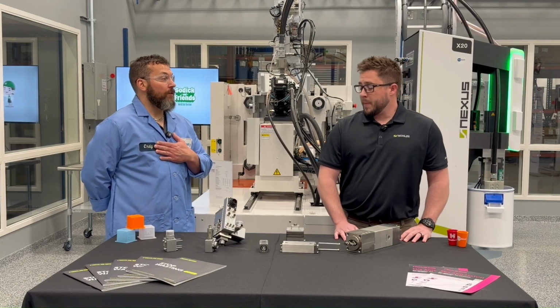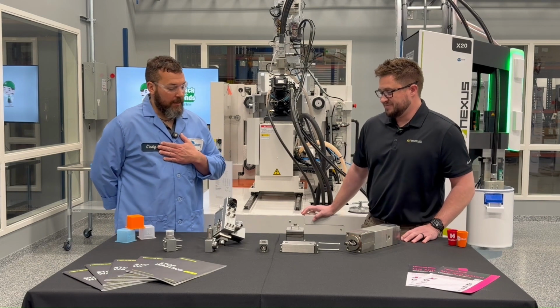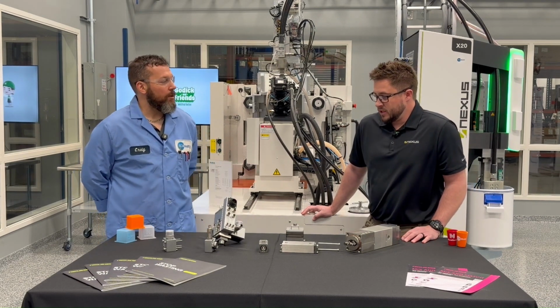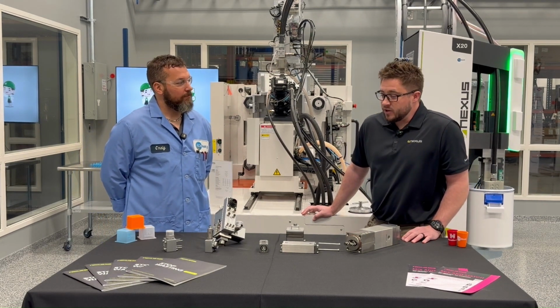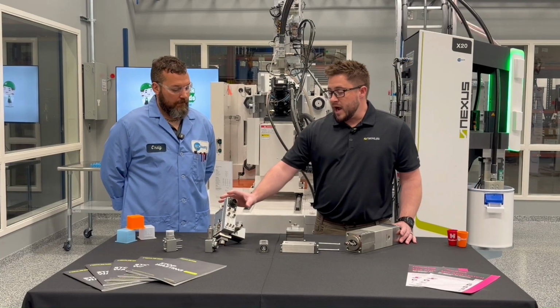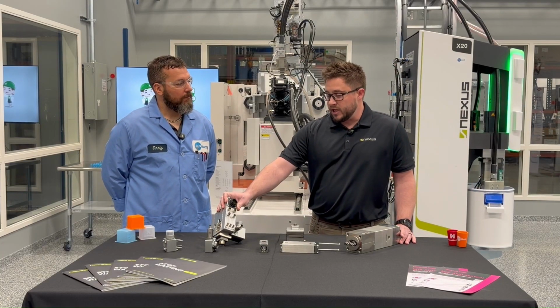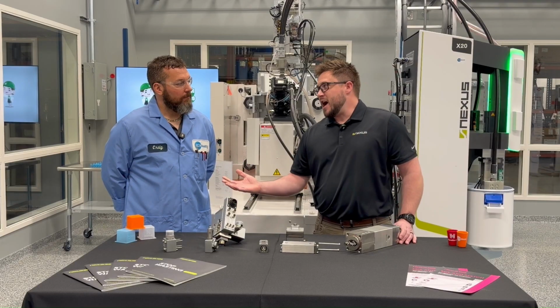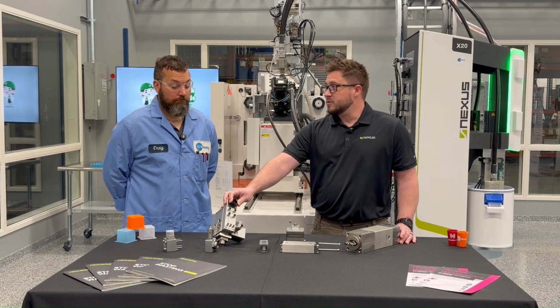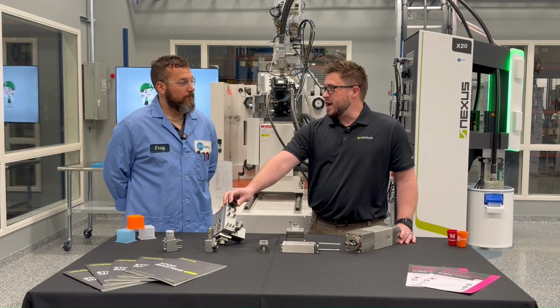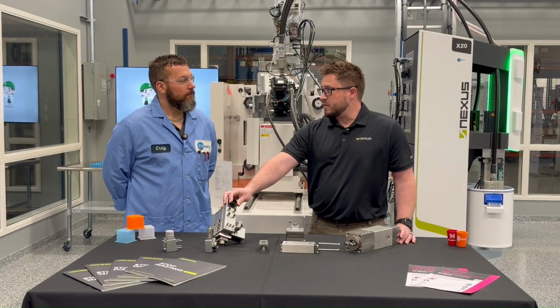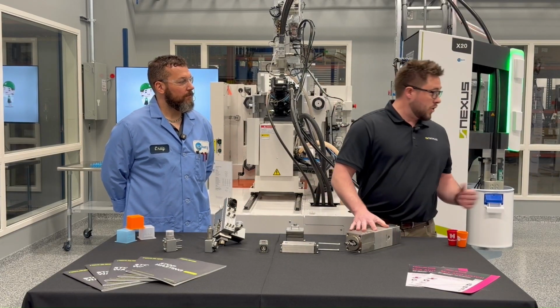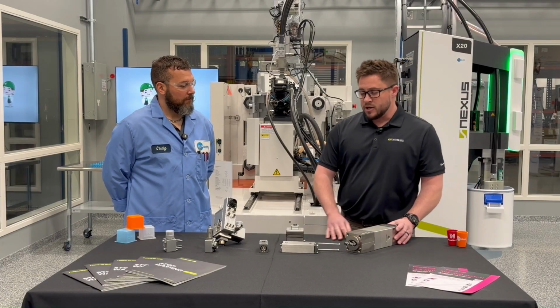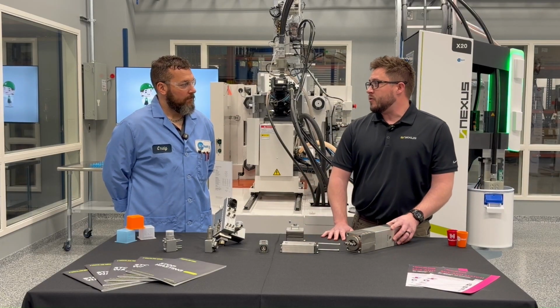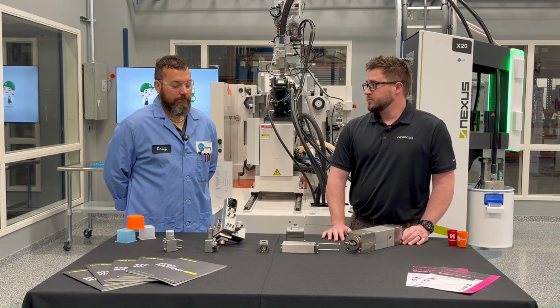One thing I've experienced as a novice—how long does it take to tear all this apart and clean on average? Without color, you can have this taken apart, cleaned, and put back together as a novice within about an hour or so. With color, add a little more time, maybe an hour and a half. The pump system, including the flow meter, would also take about an hour to an hour and a half per side.